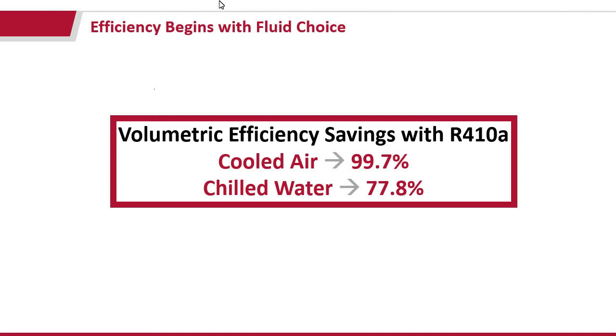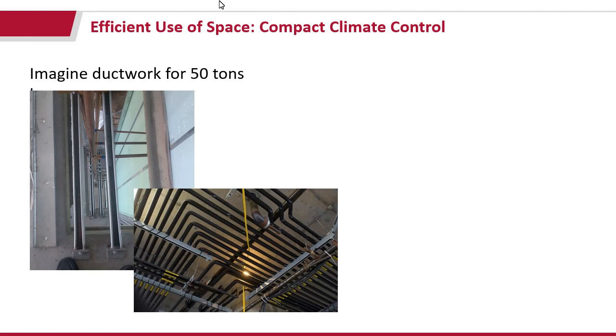And so if you have projects where you need something that's going to take up a lot of space, this is a great thing to consider because you have that efficiency of keeping that refrigeration cycle the only heat transfer cycle. Like you're not trying to transfer heat or cooling to air that doesn't want to accept the energy as readily as refrigerant wants to. So let's just look at this really quick.